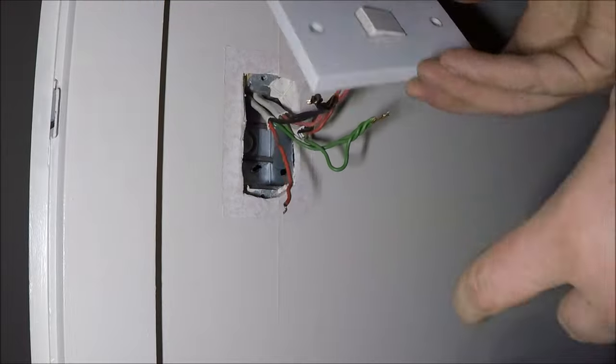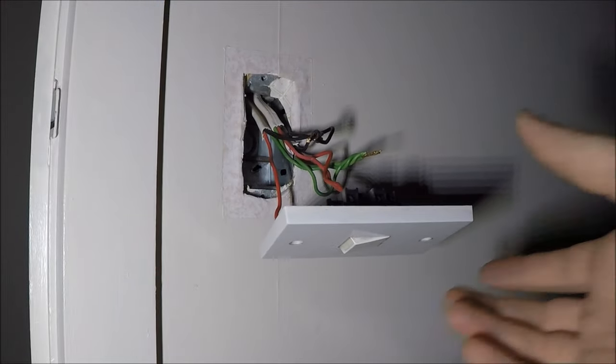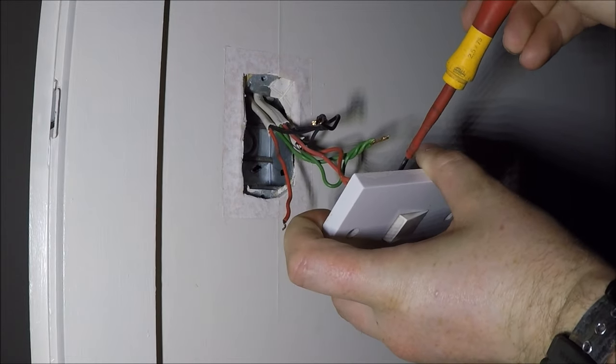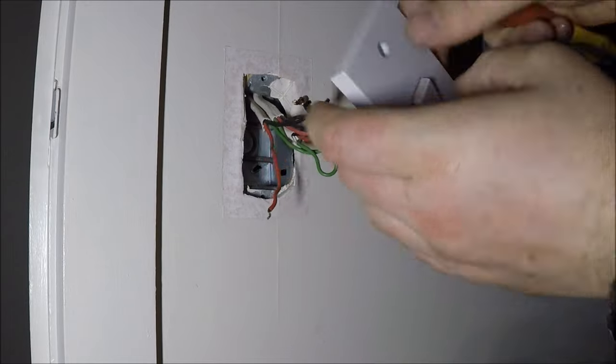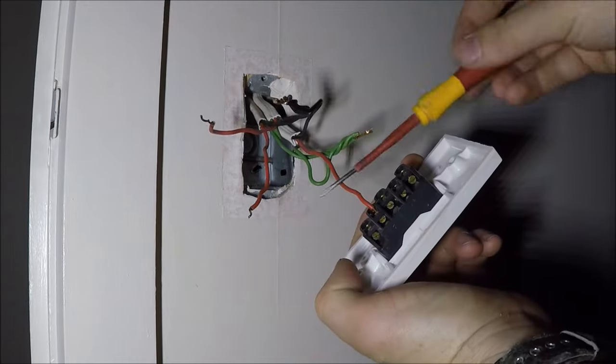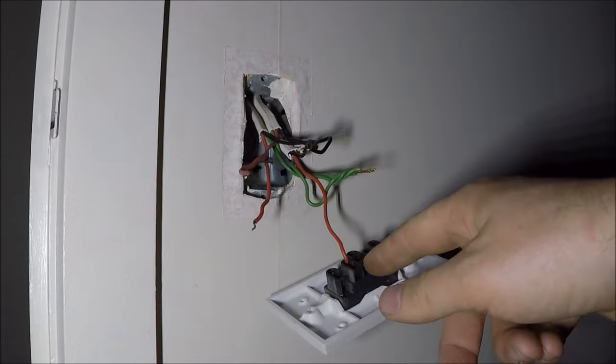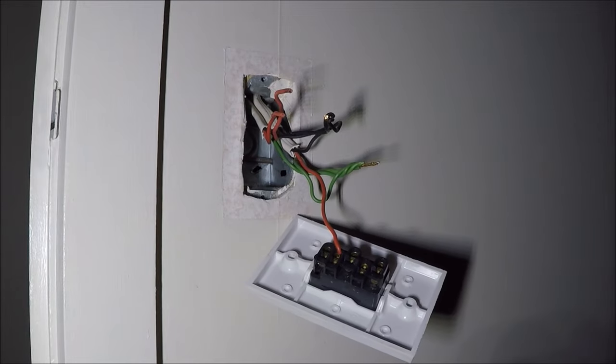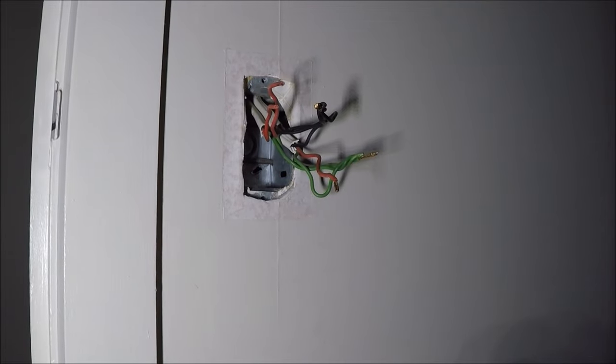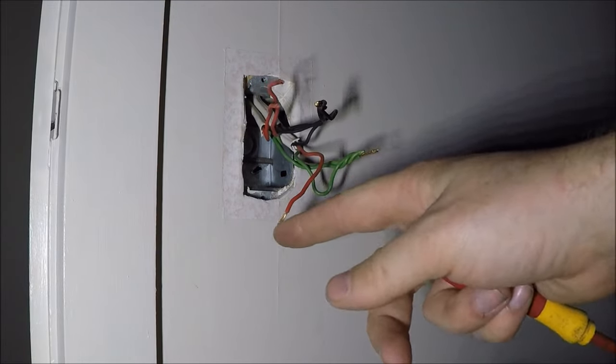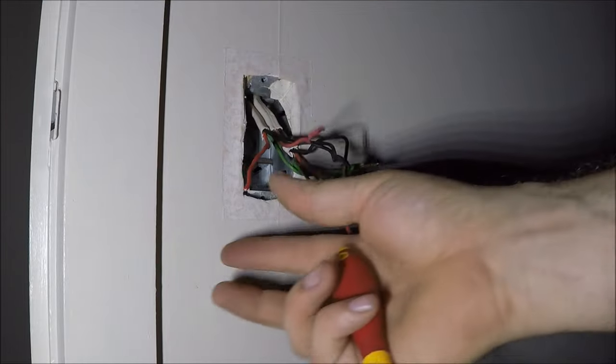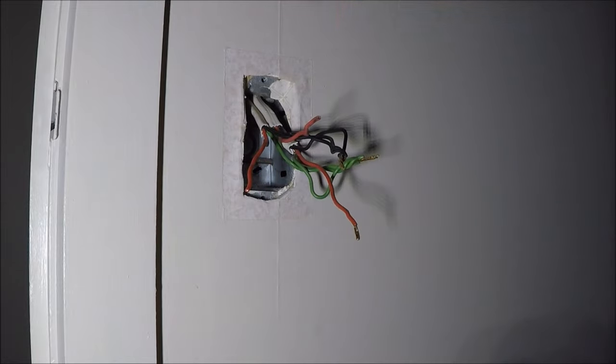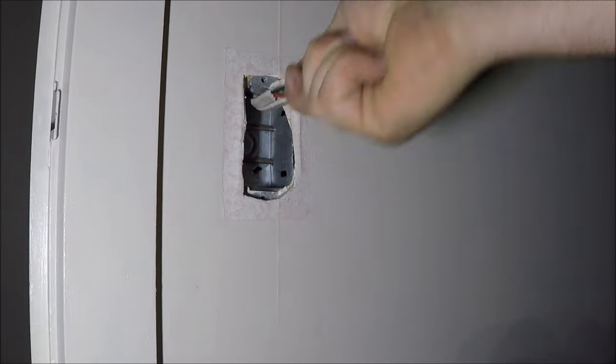Oh see, you can see that cable snap there. That's what you've got to look out for with these one-mil cables. That's why you should re-terminate them every time you remove a fitting. These two here are obviously the feed cables, because I know there's only one light on the lighting circuit, and that one cable goes to that one light. These two here were in the middle terminal labeled C, so the two cut ones are my feed, and the one with copper still on it is my light switch cable. So that's the cable that goes directly to the light fitting. These two, one of them will run back to the switchboard, probably through other light switches, and then one of them will run off to another light switch to power that one.